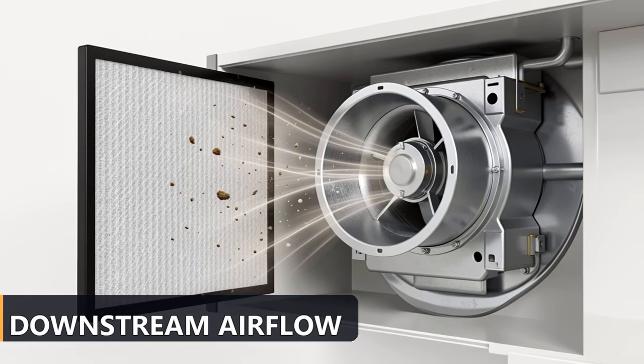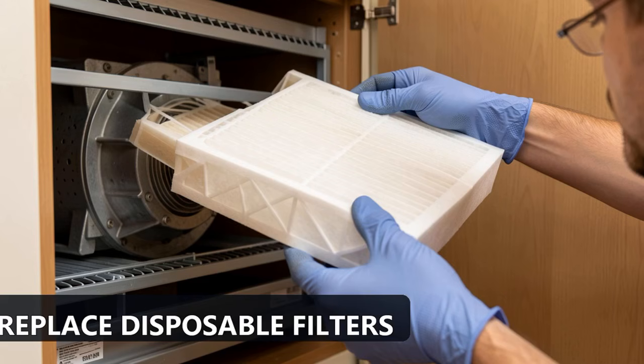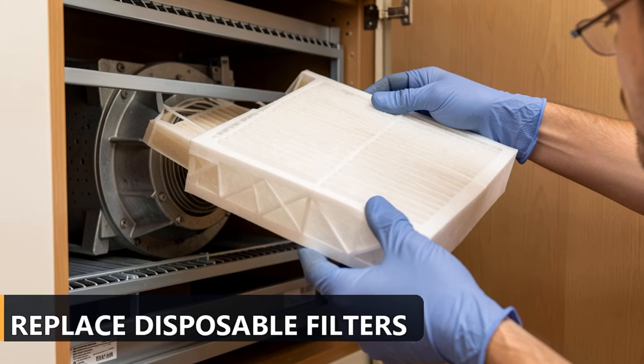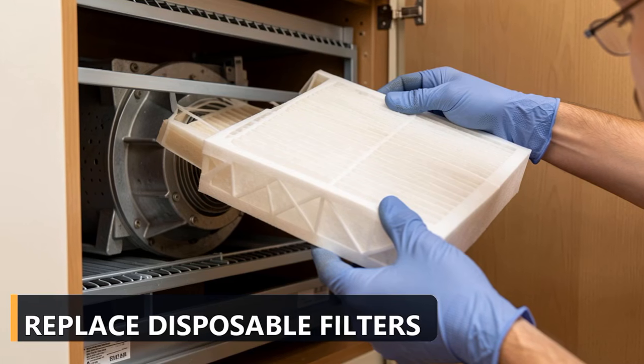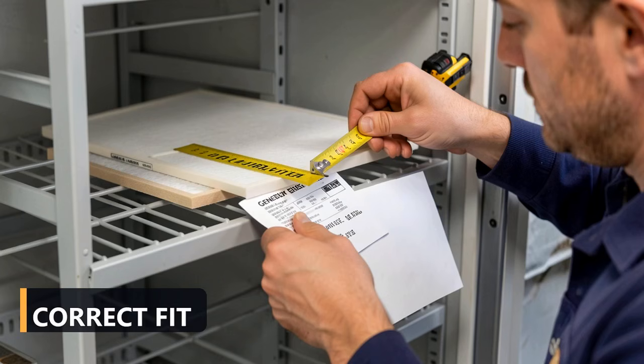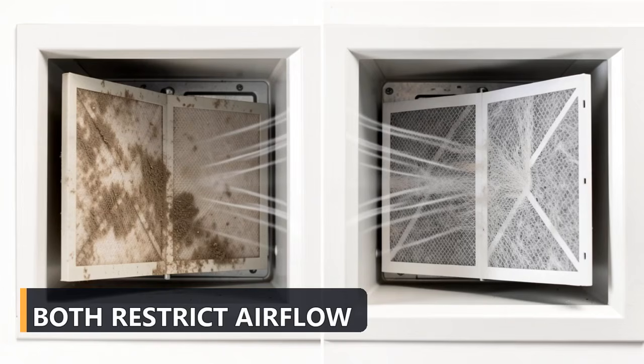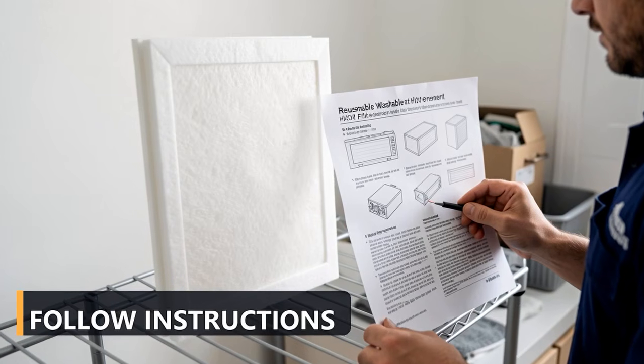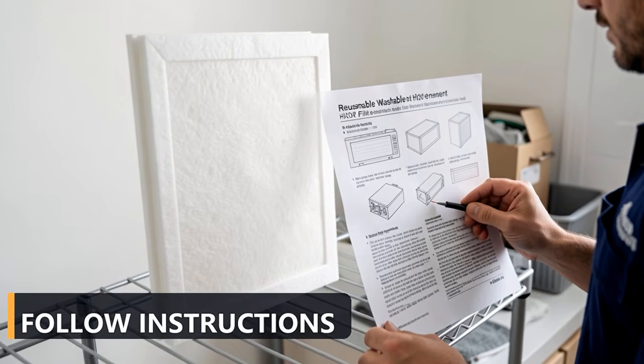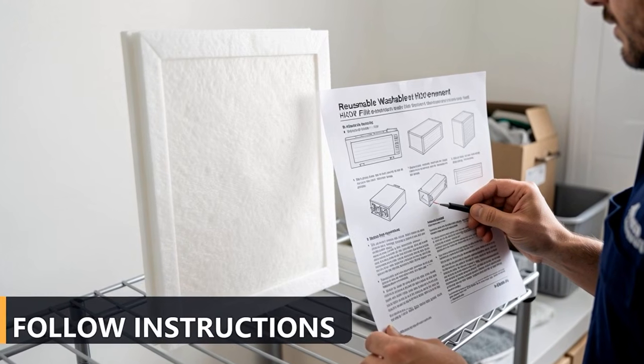If the filter is labeled disposable, replacement is the maintenance procedure. Match the correct dimensions and a filtration rating suitable for the system. A filter that is too restrictive can reduce airflow just as surely as a dirty one. If the equipment uses a washable permanent filter, follow its cleaning instructions and allow it to dry completely before reinstalling it. Do not invent a peroxide treatment simply because the material looks reusable.